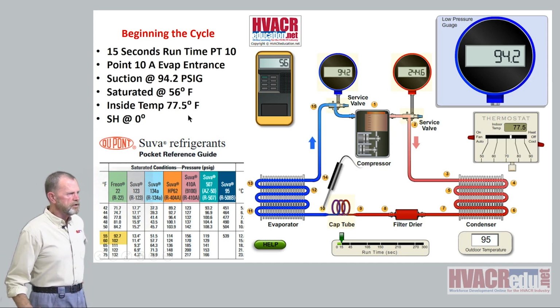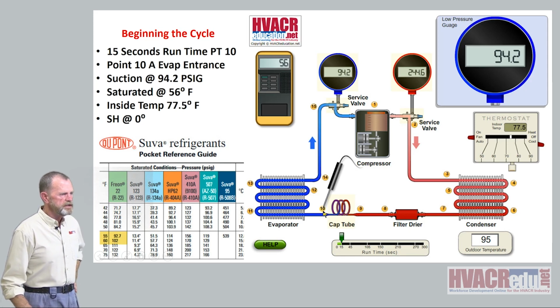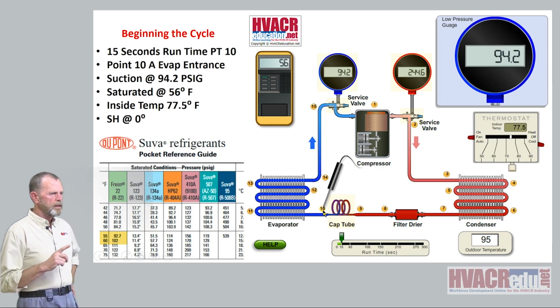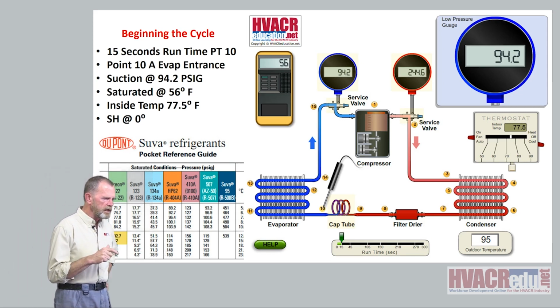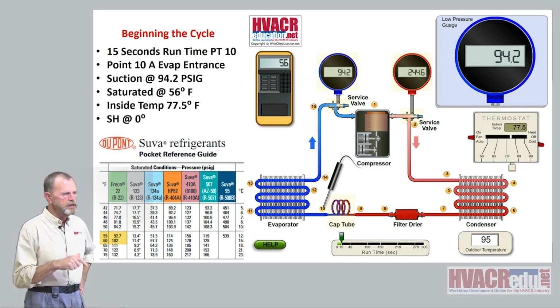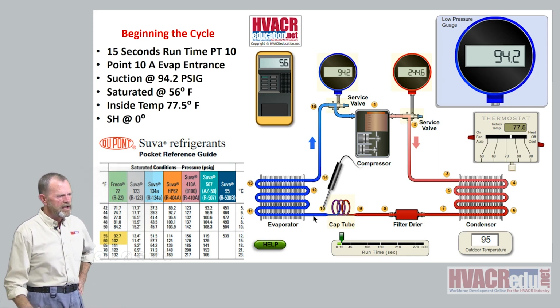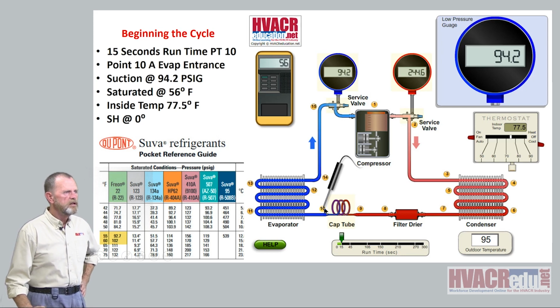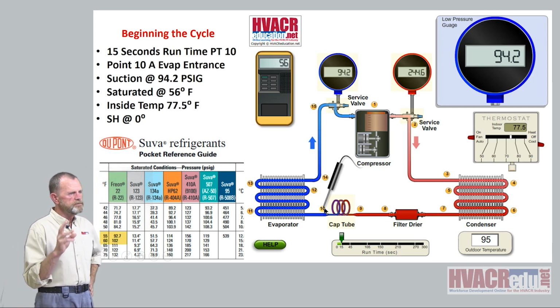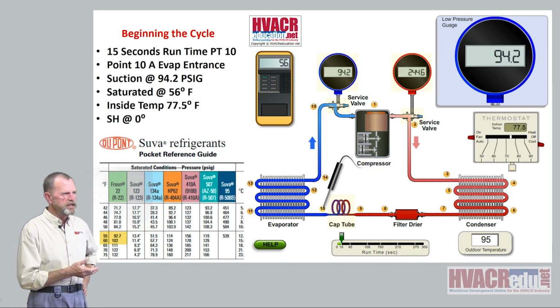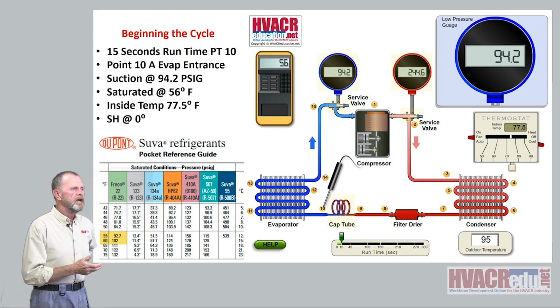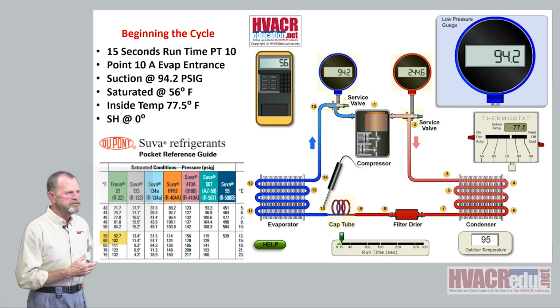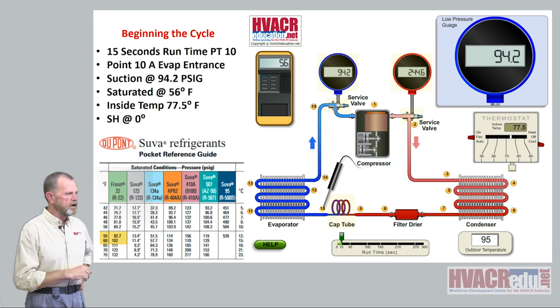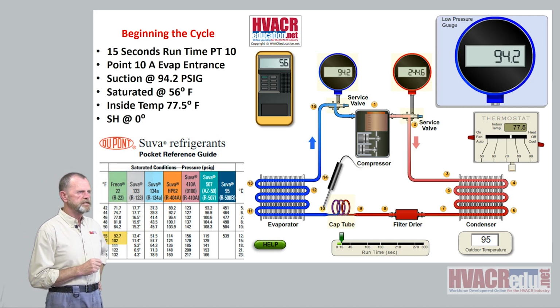The inside temperature going in is 77.5. I'm measuring right here at the inlet of the evaporator. And I will tell you that if you have a system running, if there is any saturated condition anywhere, it's going to be at the inlet of the evaporator, because that's where the first liquid comes into the evaporator. You've had the pressure drop through the capillary tube or the metering device, and it's at 94.2 pounds in there. Boom, the R22 is our example. R22 is going to flash off and evaporate at 56 degrees Fahrenheit.